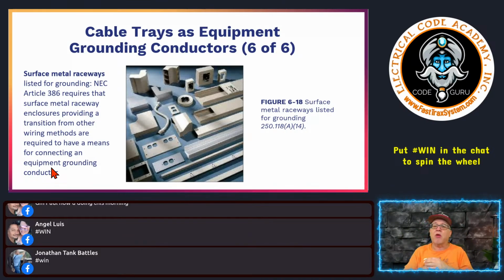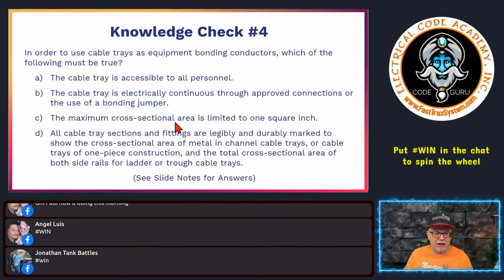But again, follow the instructions from the surface metal raceway. It may say otherwise. But if it's metal to metal, and we're talking feeders and branch circuits, and typically for this type of stuff you see on the screen, probably going to be branch circuits, then you should be okay to use the listed fitting and a lock nut and transition from metal to metal, okay? But again, always follow the manufacturer's instructions. Just saying. Be safe, better safe than sorry.